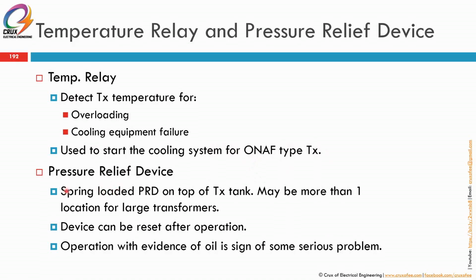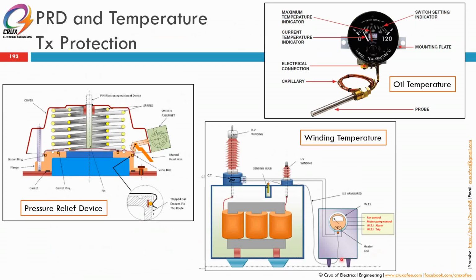Alright. Then we also have the pressure relief device. It's a spring-loaded PRD on top of the transformer tank. May be more than one location for very large transformers. Device can be reset or it may self-reset after operation. An operation with evidence of oil is a sign of some serious problem. So this is a pressure relief device normally located on top of your transformer main tank.